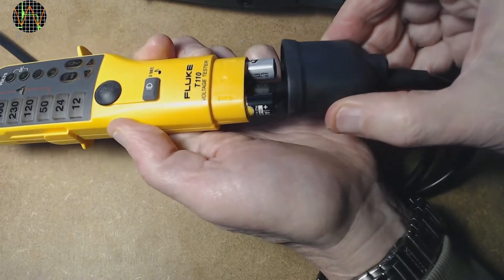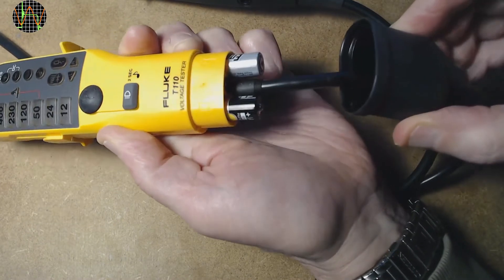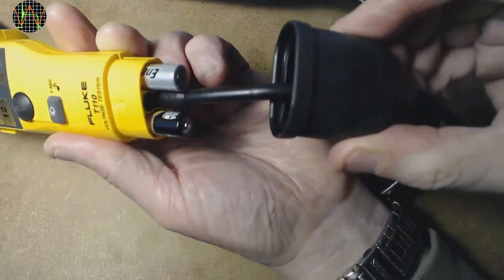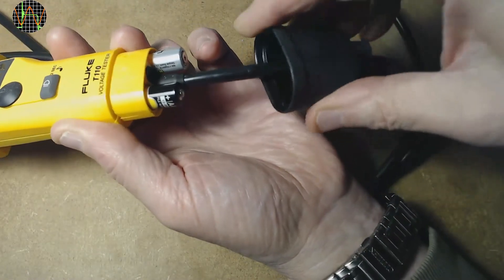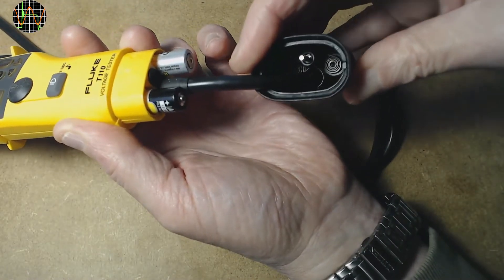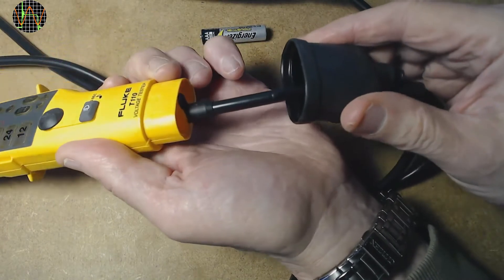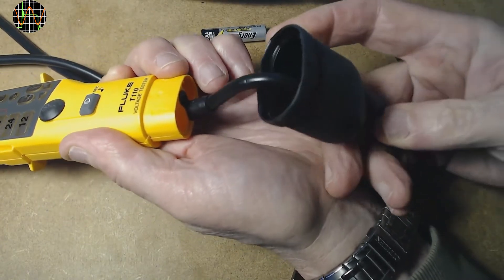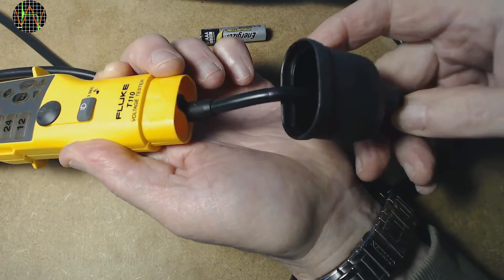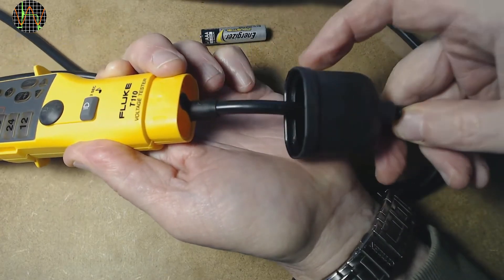Apparently there is an issue with the strain relief of the connecting cable which can cause the tester to fail intermittently to detect dangerous voltages. Also, Fluke detected that the cable itself may fail under repeated bending stresses far earlier than what they consider an acceptable useful life.